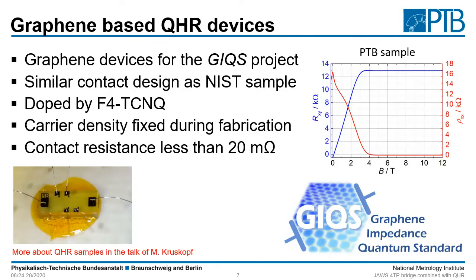At PTB we are also producing graphene based quantum hall devices and we are involved in the graphene impedance quantum standard project, which is a European metrology project. The contact design of our samples is quite similar to that of the NIST samples, but in contrast we dope the samples with F4-TCNQ, which means the carrier density will be fixed during fabrication. Looking at the overview plot, you can see that also for this sample the quantized state at DC is achieved at fields above 5 Tesla.